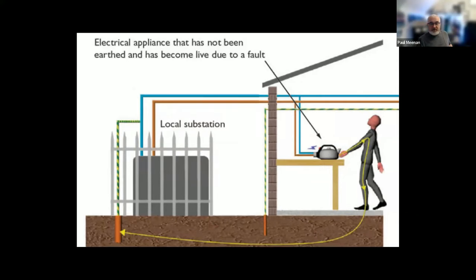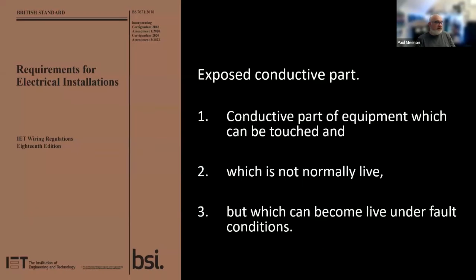Now, what happens if you don't earth the appliance? So maybe the same kettle, but there's no earth connection. And I know in India you have different practices, so let me get onto this and we'll maybe talk about it. So with electrical appliances that have not been earthed, you provide that fault path. You will effectively receive either an electric shock, which will cause you harm, or you will be electrocuted and die. So there's no in between really, to be honest with you. Either you get very lucky or you get dead. So earthing is incredibly important because the current will take the path of least resistance through you down to the ground. And you then have to hope you've selected your devices accordingly, which we'll come on to.